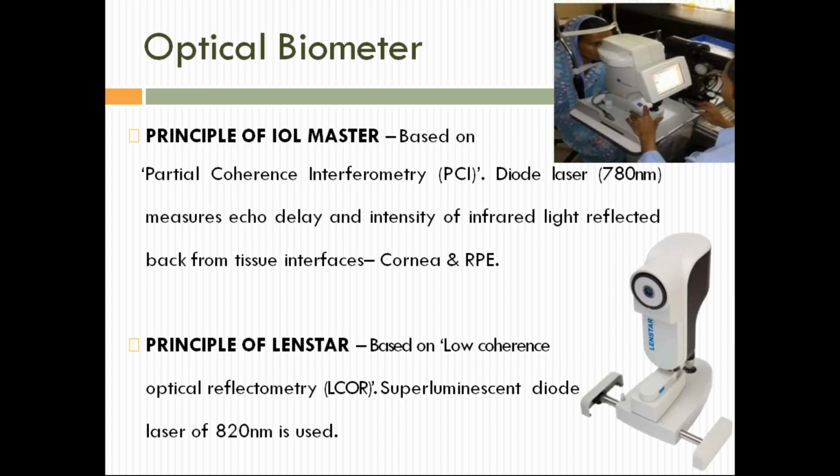The principle of IOL Master. It is based on partial coherence interferometry, 780 nanometer. It measures echo delay and intensity of infrared light reflected back from the tissue interfaces, cornea and RPE. Principle of LENSTAR. Based on low coherence optical reflectometry, it uses a superluminescent diode laser of 820 nanometer.